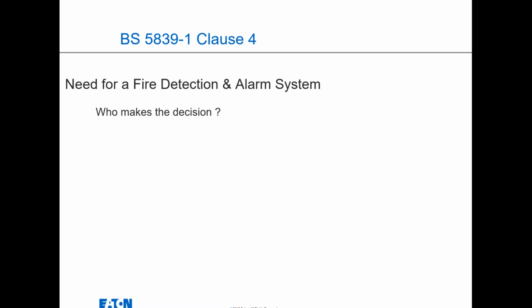So when we talk about the need for a fire detection, who should make that decision? Well, the developer, the purchaser, the user, in consultation with other stakeholders, such as insurance companies, and obviously driven by a risk assessment, which forms part of the regulatory reform order, which we touched on earlier, which is law. So if you own a building, you should have a risk assessment in place, and that risk assessment should cover the fire alarm system, and then that would lead to telling you what need you have for a fire detection system. And we'll come on to the types of fire detection systems you need.